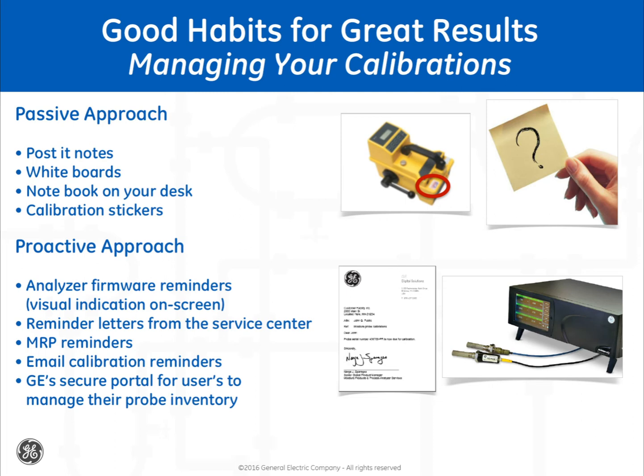Some companies use calibration stickers. These are passive devices. In the field, the sticker has no ability to call out for service, nor to provide insight as to the criticality of the measurement. We offer analyzer firmware reminders to provide visual indication of the need for calibration. The technician will still need to refresh the calibration dates in the analyzer upon installation of new sensors or recalibrated sensors. In the above cases, there is no relationship with the vendor, leaving the customer on their own to ensure the maintenance and calibration of the sensors.